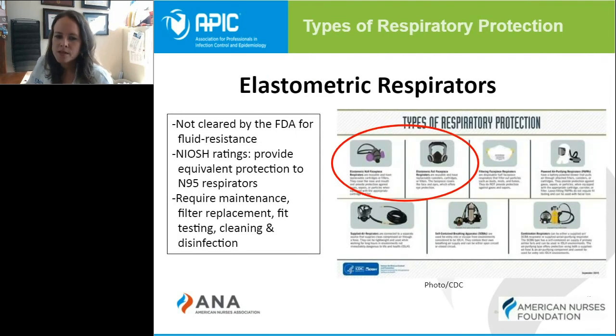The elastomeric respirator is one to point out because it is not cleared by the FDA for fluid resistance, even though NIOSH rates it as equivalent protection to an N95 respirator. These masks require additional maintenance, including filter replacement, fit testing, cleaning, and disinfection. They should be evaluated carefully in your facility if you are assessing whether or not to use them.